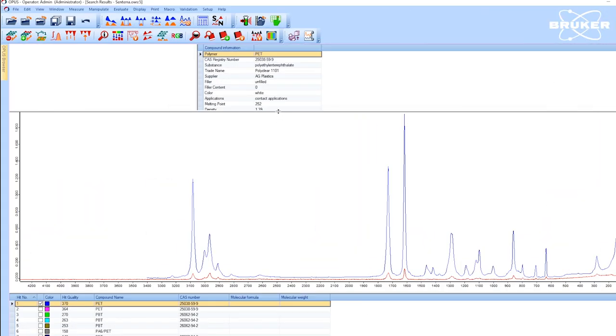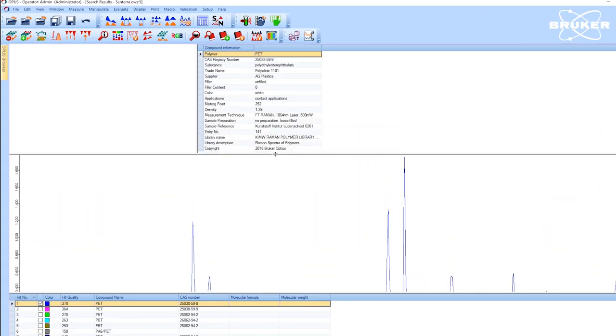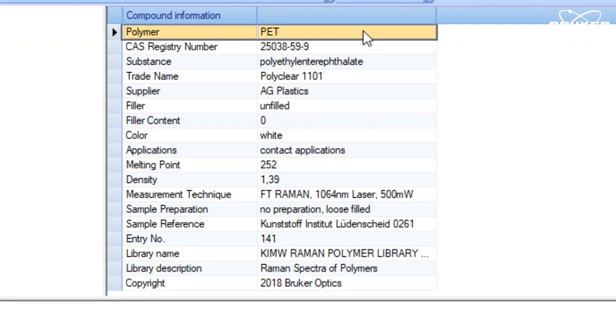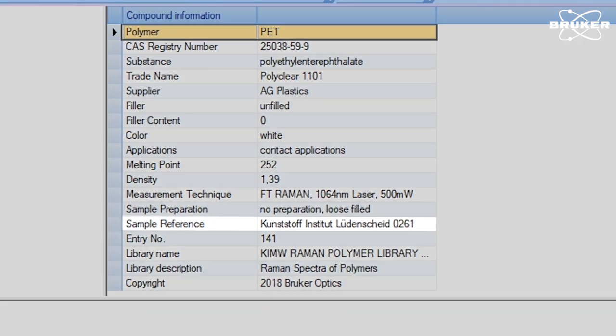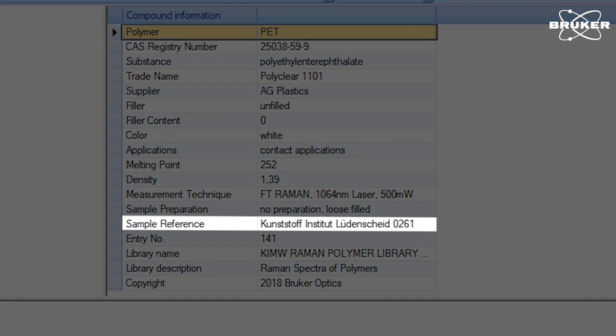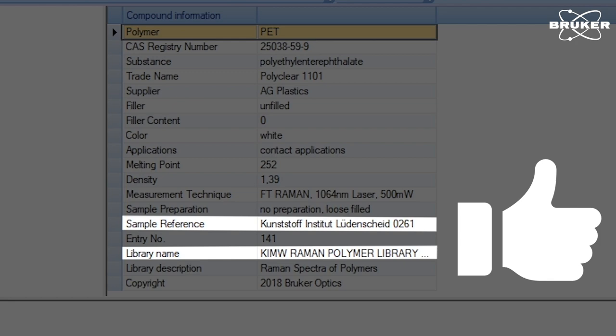Identification is performed by applying a special polymer spectral reference library by the Polymer Institute Lüdenscheid. Together with Bruker Instruments, they created a carefully compiled Raman and FTIR reference library that only contains relevant, up-to-date polymer materials.